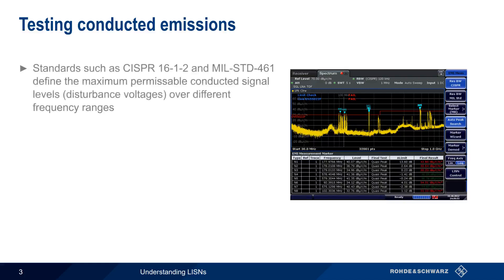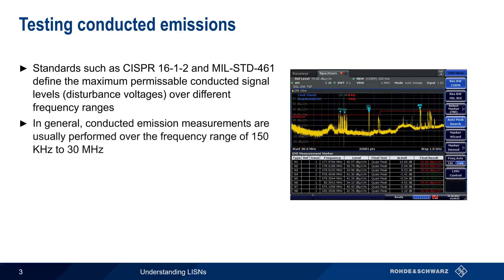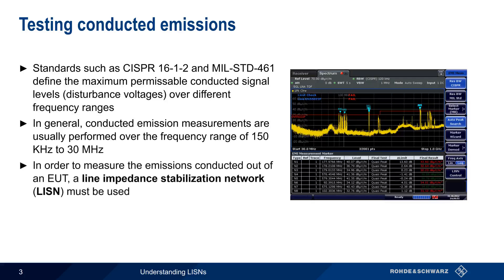So how do we test for conducted emissions? EMC standards, such as CISPR-16-1-2 and MIL-STD-461, define the maximum permissible conducted signal levels, also called disturbance voltages, over different frequency ranges. For the most part, conducted emissions testing is carried out over the frequency range of 150 kHz to 30 MHz. In order to measure the emissions from an EUT, or equipment under test, a special device called a Line Impedance Stabilization Network, or LISN, must be used.